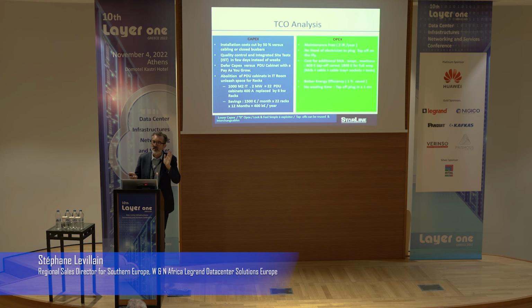For OPEX, it's maintenance-free, so you save money on infrared testing - no need to do that. When you need to connect a new rack, you can do it yourself. You buy a tap-off, around 600 euro on average. But if you need electrical guys to come, open the raised floor, put in new cables and cable tray, I'd say 1.8 kilo isn't enough - you can perhaps multiply by 2 if you need someone on site to do the job. So there's a lot of difference, something to consider.